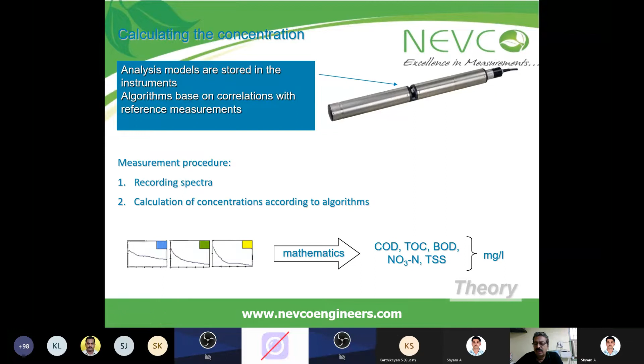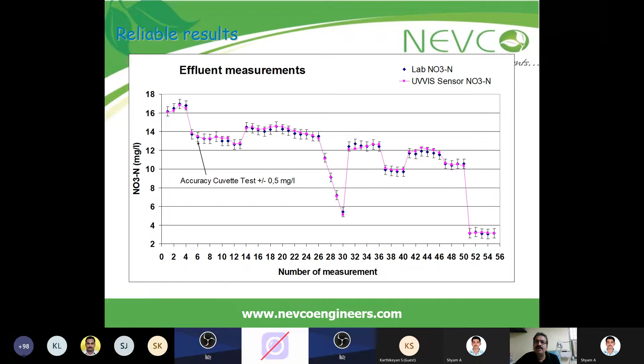You can analyze the models stored in the instrument. Algorithms are based on correlations with a reference measurement. It has a reference measurement, and you can calculate how much exactly. You can see the measurements from lab readings versus your analyzer readings. You can have a comparison of UV-visible sensors to a lab measurement and an analyzer measurement.